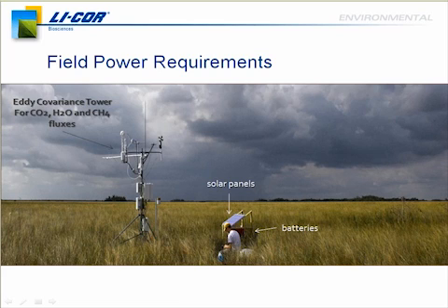All of these instruments and the sonic anemometer, the ancillary meteorological instruments that you see there, and the data logger are being powered off those solar panels in the image and the battery pack there. So again, we just think it's really significant that the LI-7200, along with the flow module, can provide you with the measurements that you need and only require about 27 watts of power. So this is, again, something that we think is a significant step forward in being able to get the measurement made where you need to make it instead of where the infrastructure allows you to make it.